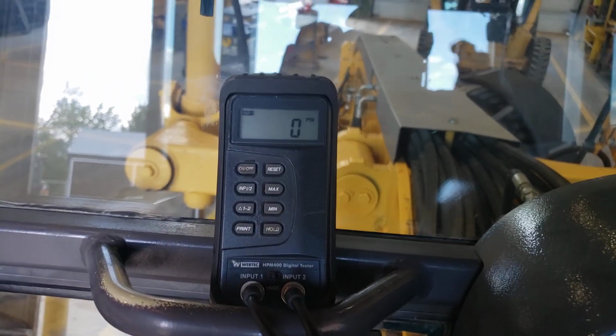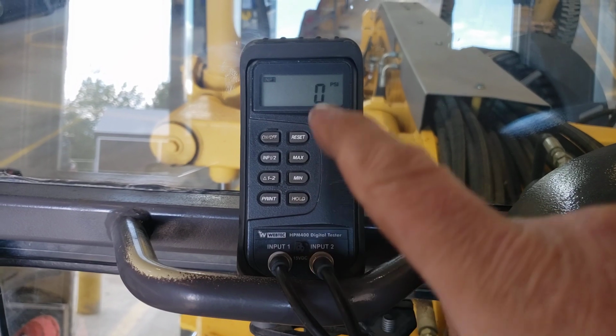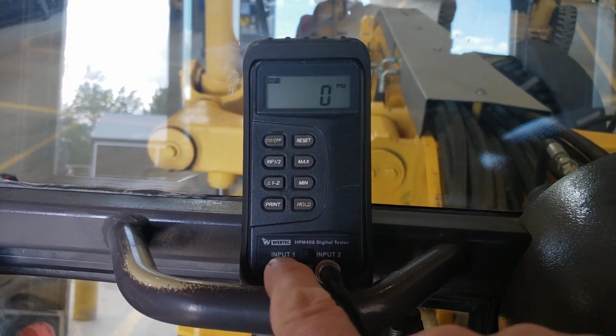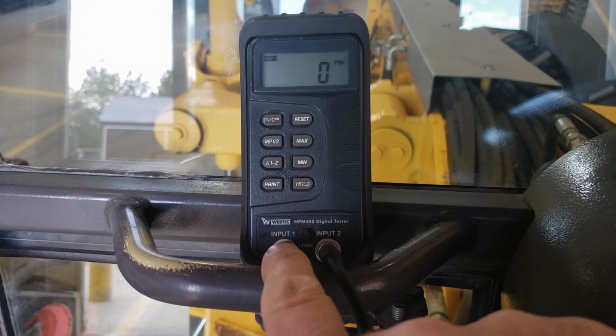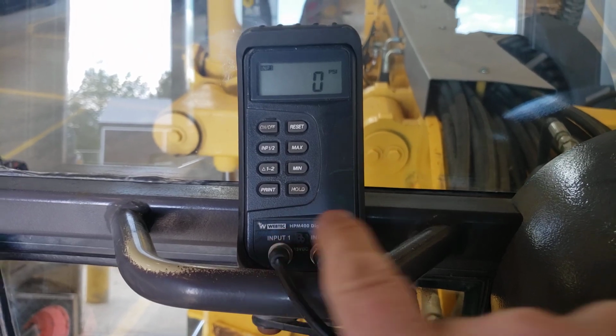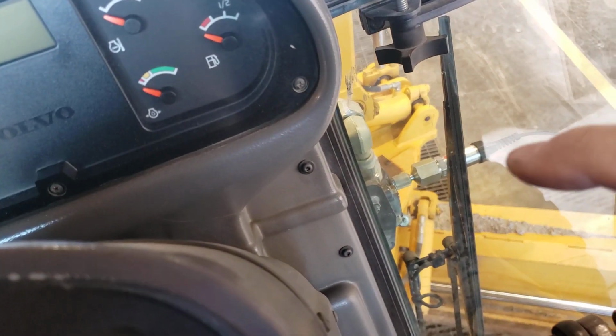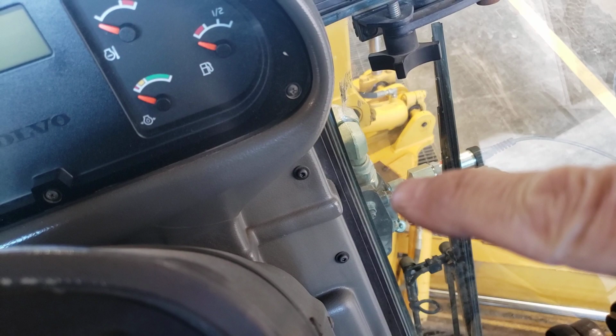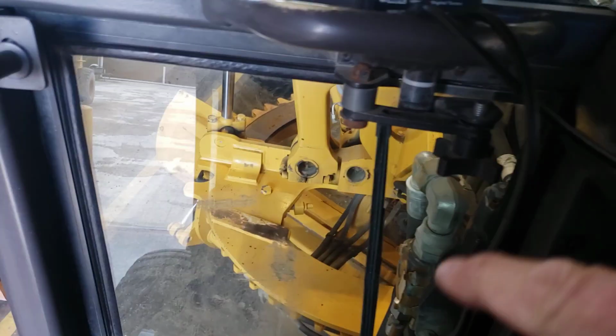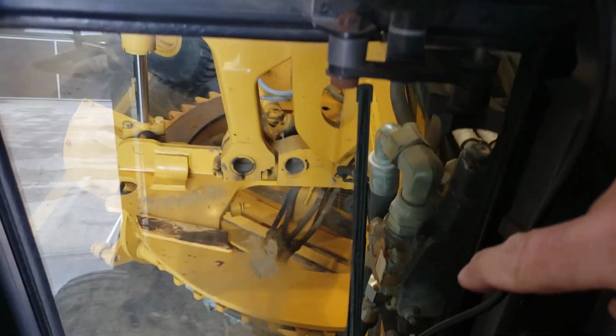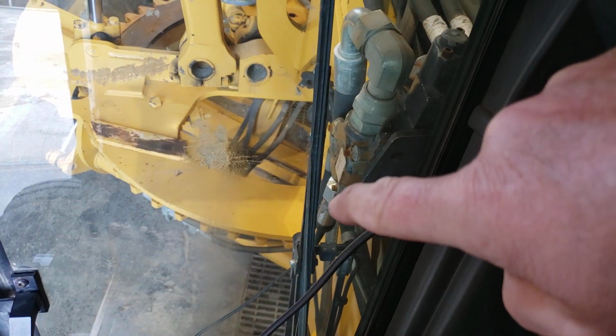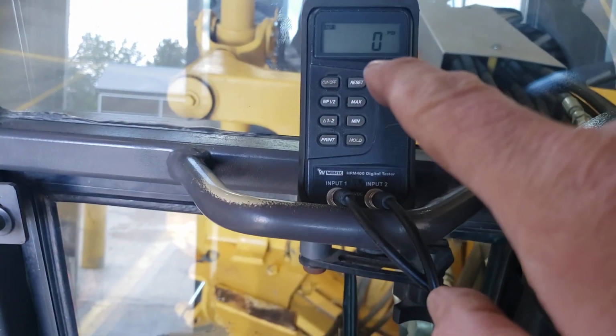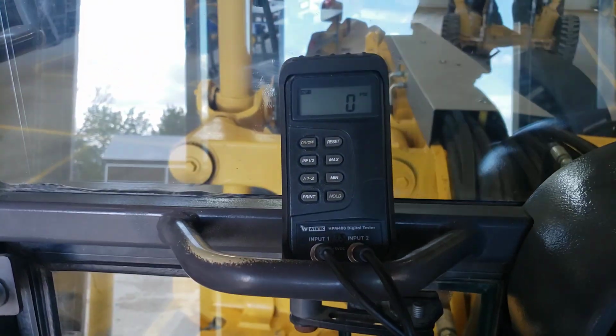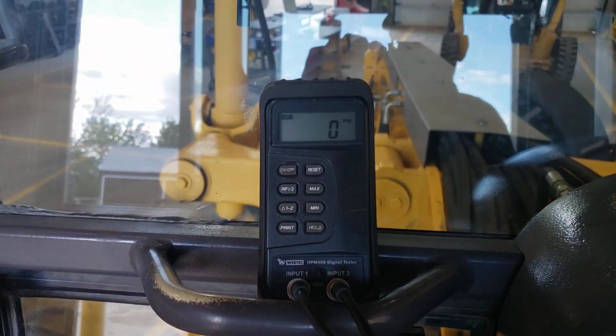So now I've hooked up both gauges into one. If I don't want to be doing the math all the time in my head, this tool will do it for me. So input 1, I've still got connected to the pump discharge pressure, the supply to the 10-bank valve. And then input 2, I've got connected to the load sense signal. If I got these backwards, it would just read a negative number for the difference. I'll start this up and we'll see what we get.